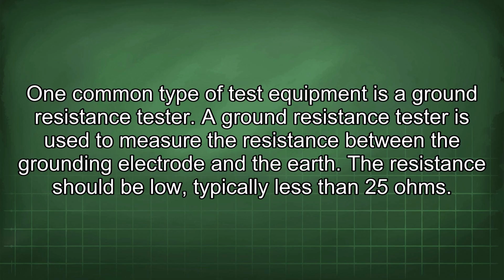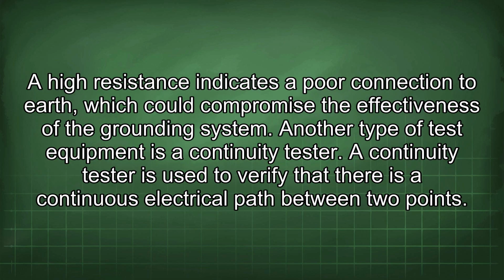A ground resistance tester is used to measure the resistance between the grounding electrode and the earth. The resistance should be low, typically less than 25 ohms. High resistance indicates a poor connection to earth, which could compromise the effectiveness of the grounding system.